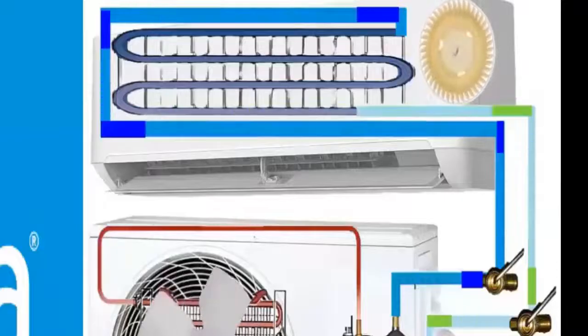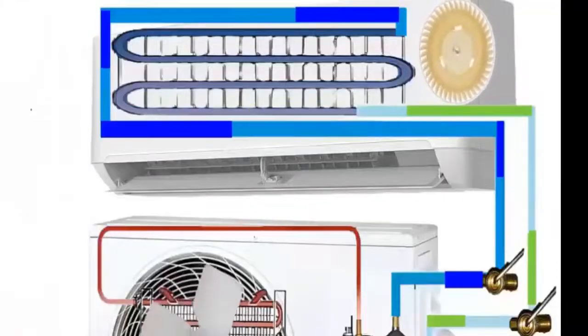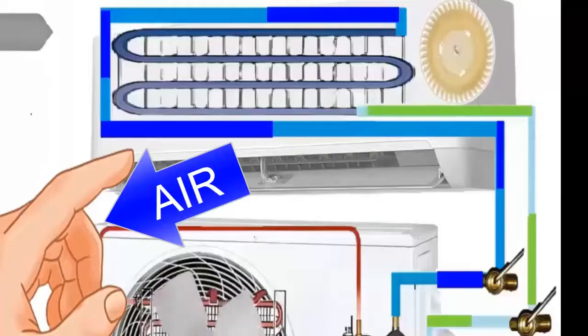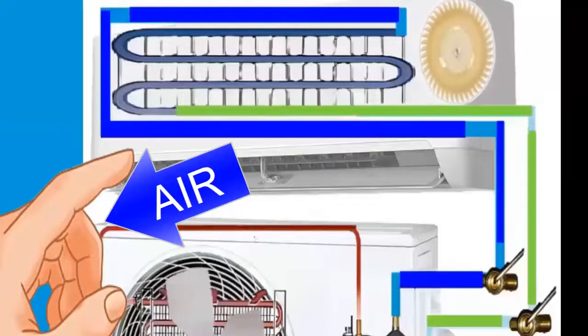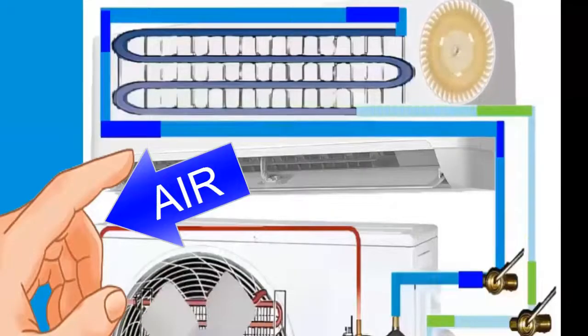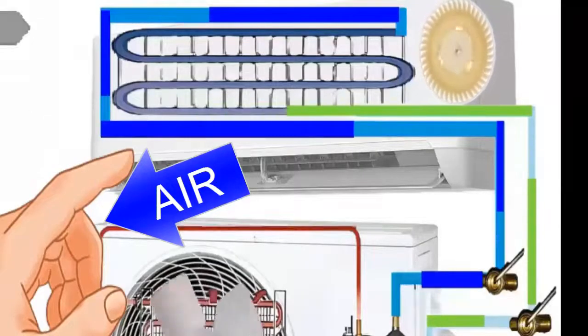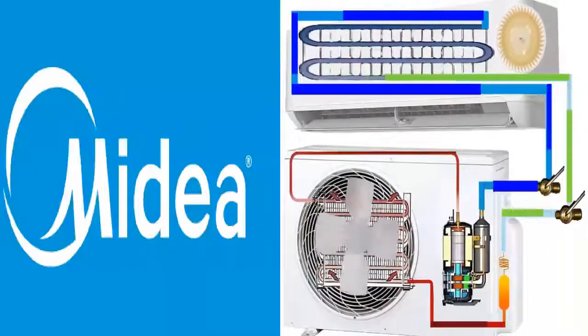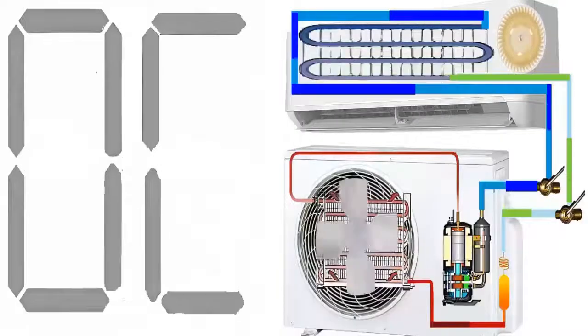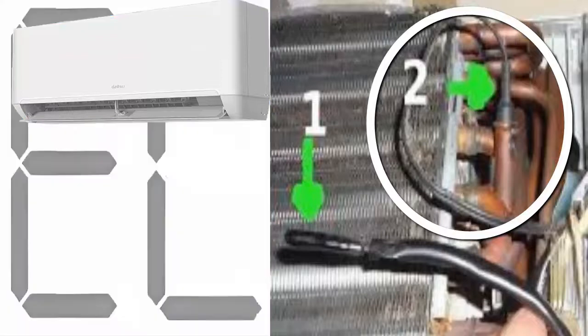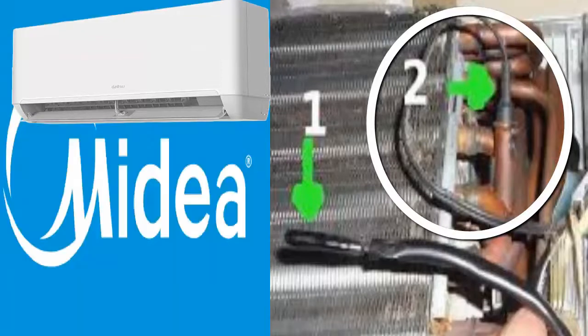Step 3: If the air coming out is sufficiently cold, there is probably no refrigerant gas leak, and the issue might be a false alarm. Step 4: To identify the cause of a possible false alarm, focus your diagnosis on the temperature sensor located on the coil of the indoor unit, known as the coil sensor or evaporator sensor.